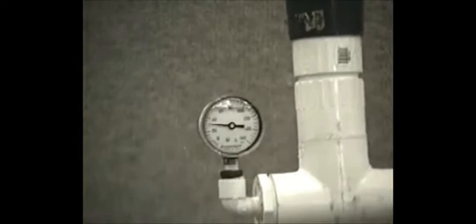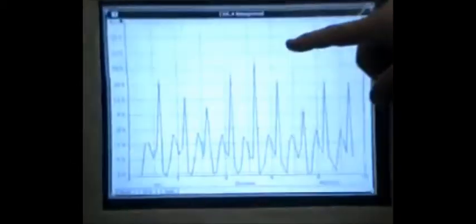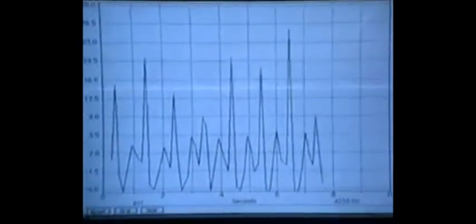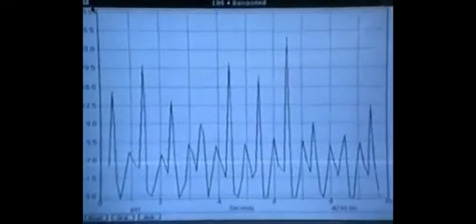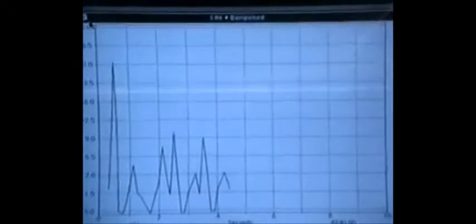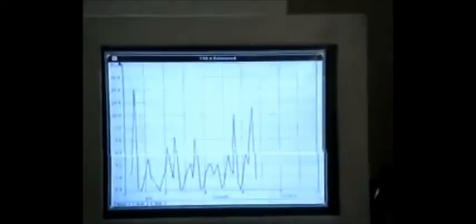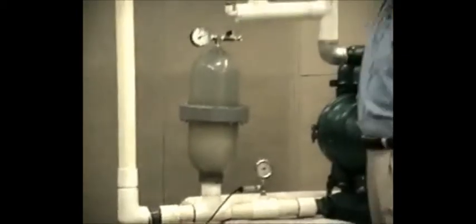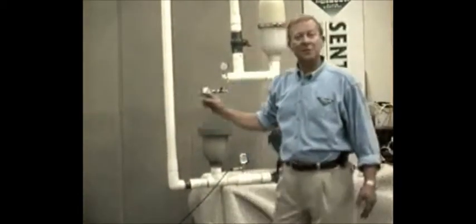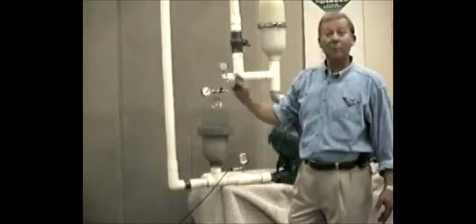The inlet side is still shaking violently and you'll notice on the transducer that the pressure spikes are reaching as high as 19 psi. Now most air-operated diaphragm pumps tell you in their instructions not to exceed 15 psi with rubber diaphragms or 10 psi with teflon diaphragms. So you can see that we can be doing damage to the diaphragms with this kind of pressure spike.